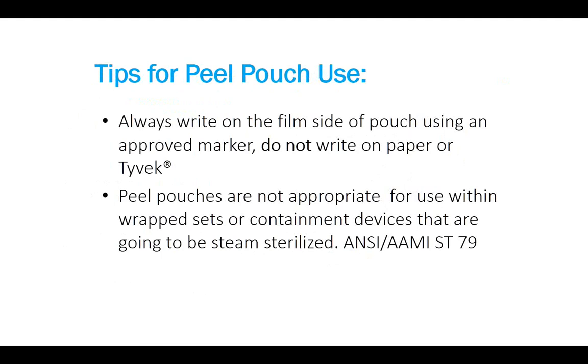Also, write on the film side of the pouch, using an approved marker. Do not write on the paper side or the Tyvek side. That will bleed through. You don't want bleeding. Peel pouches are not appropriate for use within wrap sets or containment devices such as containers that are going to be steam sterilized. That's per ANSI ST79. Again, I'm just going through some basic tips.